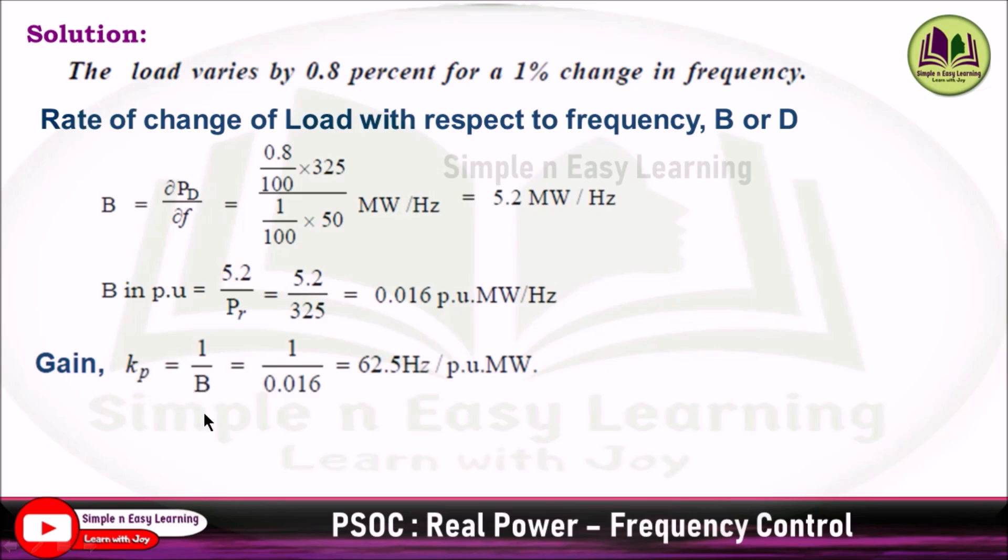Gain Kp equals the inverse of B, which is 1 divided by 0.016, equal to 62.5 hertz per per unit megawatt. Time constant Tp equals 2H divided by Bf₀, so 2 times H is 5 divided by B is 0.016 per unit times frequency 50, that gives you 12.5 seconds.